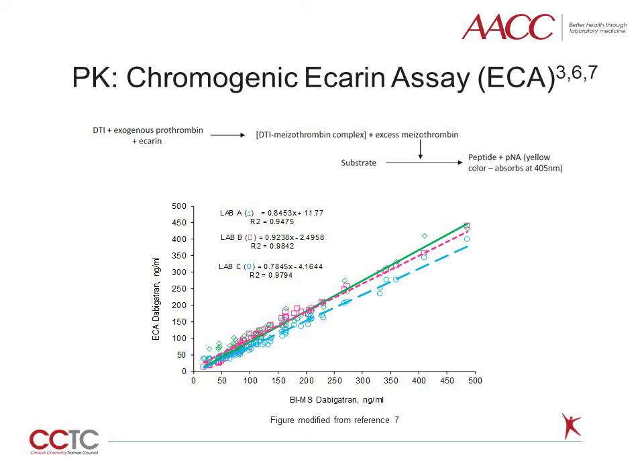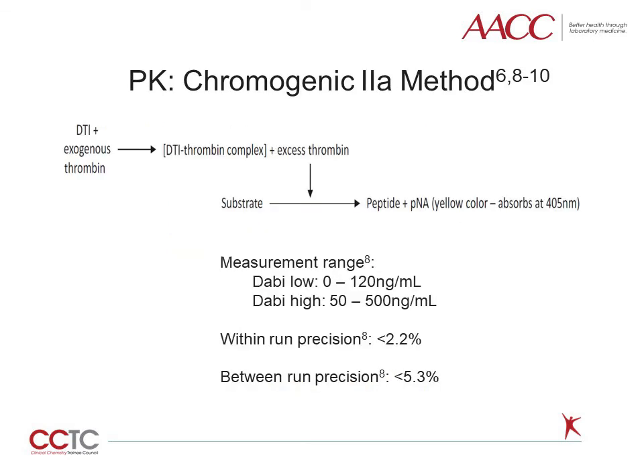The chromogenic anti-IIa method is exactly like the heparin anti-Xa assay, except the reagent is thrombin and not activated factor X. The kit is labeled RUO, research use only. The assay is easily automatable. A dual curve is needed to measure drug concentration adequately over the on-therapy range. The assay performance regarding precision and accuracy appears quite good, although there is limited published data on the method.